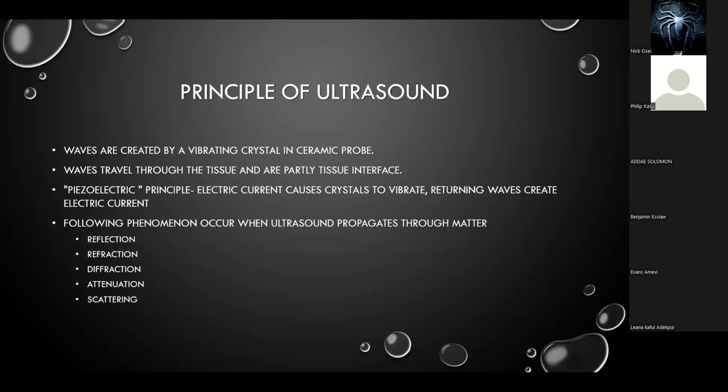So they're in the probe. An electric current is passed through these ceramic materials, and they vibrate at a very high frequency, which generates sound waves. These sound waves are channeled through whatever it is that we are studying. The returning waves that are reflected coming back to the ultrasound material are received and changed into electric current. That is what is translated on a computer screen for us to see as images.